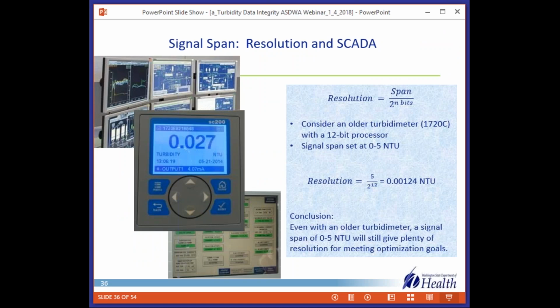Steve mentioned that almost 3/4 of the plants were capping their data below a regulatory limit. Some of our operators were reluctant to increase the span because they were concerned about resolution. They were trying to be optimized. They wanted to have really good resolution. And so we put in this slide to help answer that issue.